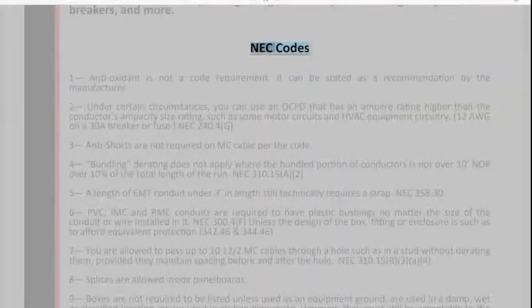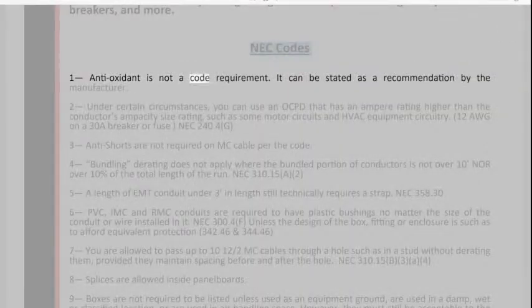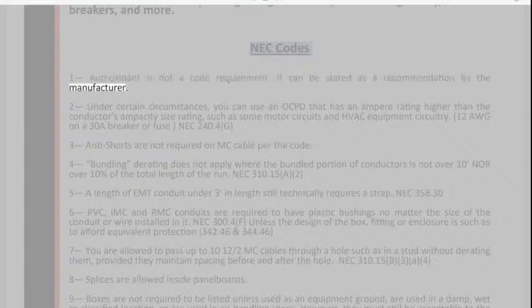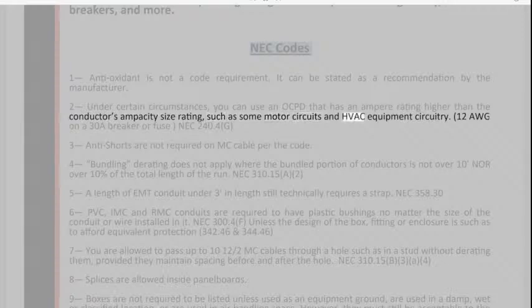Codes. 1. Antioxidant is not a code requirement. It can be stated as a recommendation by the manufacturer. 2. Under certain circumstances, you can use an OCPD that has an ampere rating higher than the conductor's ampacity size rating, such as some motor circuits and HVAC equipment circuitry. 12 AWG on a 30A breaker or fuse, NEC 240.4G.